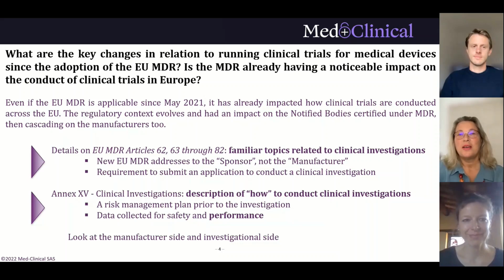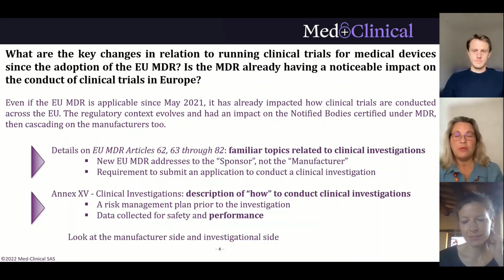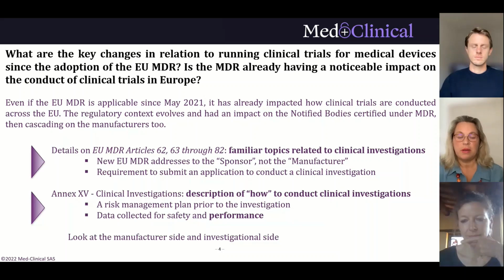Thank you. So what are the key changes in relation to running these clinical trials? Yes, it's a nice question. Even if the EU MDR is applicable since May 2021, it has already impacted how clinical trials are conducted across the EU. And the regulatory context evolves and had an impact on the notified body certified under MDR, then cascaded on the manufacturers too. And yes, you know, the MDR reinforced the PMCF process for the manufacturer, devoting Part B of the Annex 14 to it and providing a set of requirements for developing a plan necessary to implement PMCF.